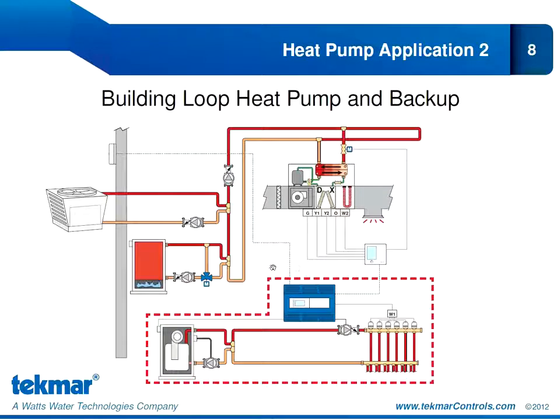We've also shown, again, the option of the radiant floor. If this is included, the radiant floor is our first stage of heat. We can find a second and third stage of heat with our heat pump, and again a possible fourth stage of heat through the electric strip backup. In cooling mode, our heat pump can provide 2 stages of cooling if it is a 2-stage heat pump.